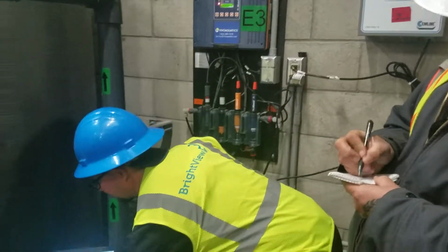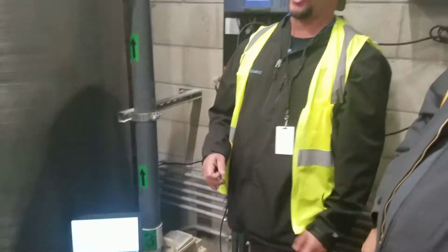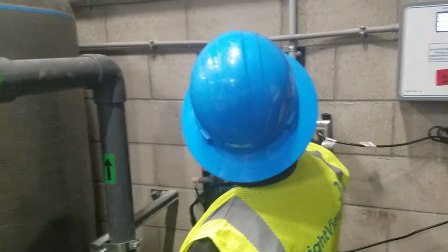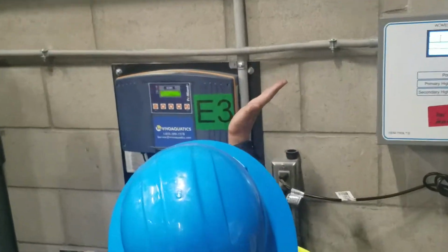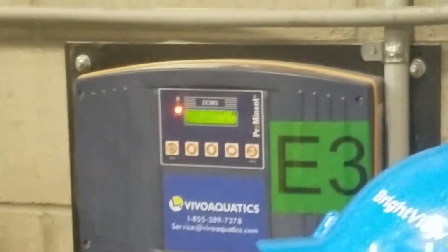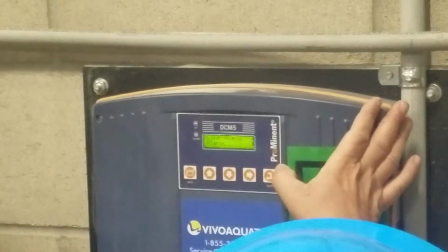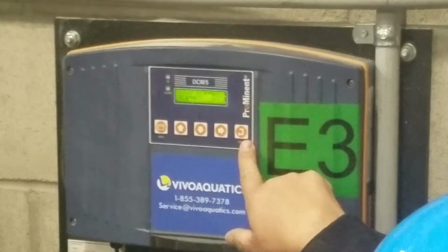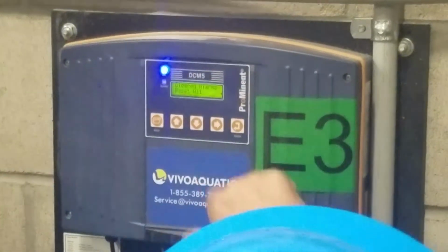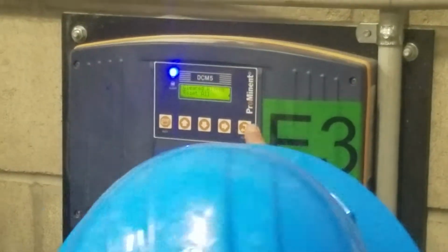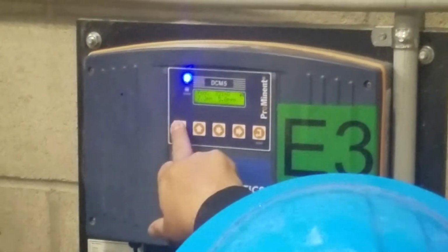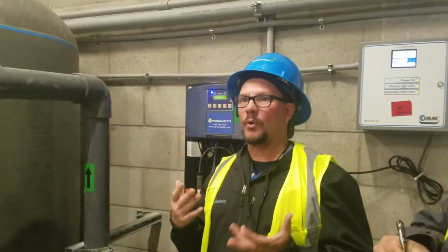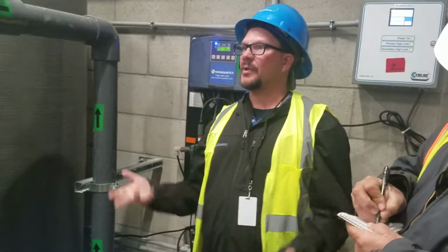So when you have an alarm like this and you validate, verify what in fact it is, and you're comfortable with doing a reset, the way you go about doing that is you will walk up to the controller, go down one time, it'll show you the alarm, you corrected the problem, what have you, and you basically hit enter 3 times. Clear alarms. You see that little hieroglyphic up there in the upper right hand corner? It's the same hieroglyphic on enter. Hit enter, it says cleared alarms, reset all. And back. Now you're back to your main screen, and you can see that it went blue. Now if that alarm still has not been corrected, it'll pop back up within 2 minutes.